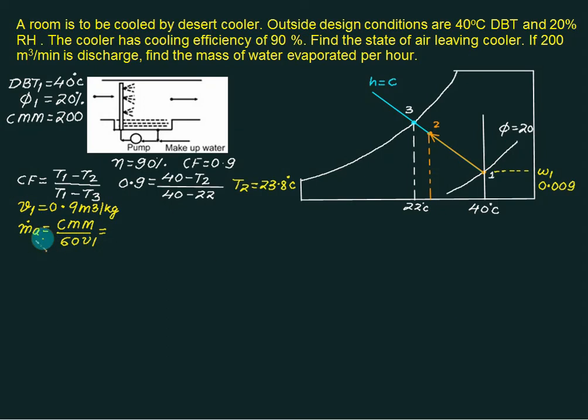So the mass flow rate of air is CMM divided by 60. CMM is cubic meters per minute, so divide by 60 to get cubic meters per second. And divide by V1 which is 0.9. So we have mass flow rate equal to 3.7 kg per second.